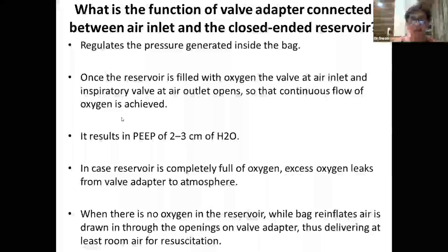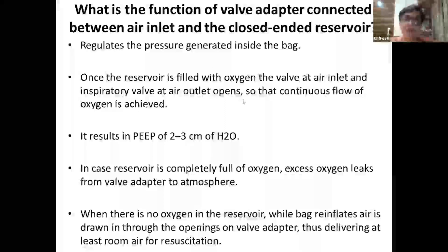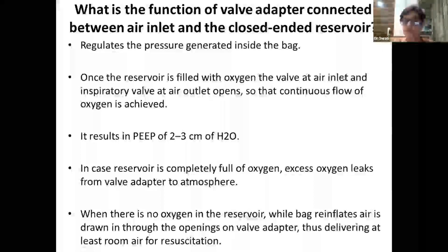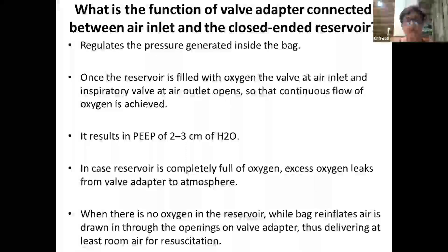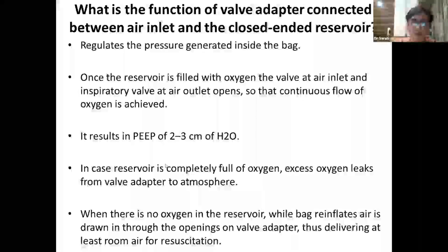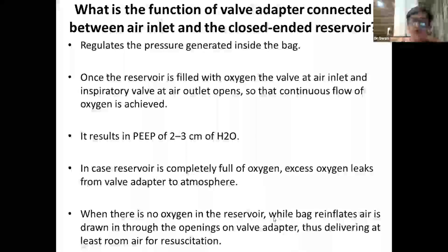The pressure regulatory valve regulates pressure generated inside the bag. Once the reservoir is filled with oxygen, the inlet and inspiratory outlet valves open, achieving continuous oxygen flow and providing a little PEEP. When the reservoir is completely full, excess oxygen leaks out to atmosphere. When there is no oxygen, air is drawn in through the valve adapter openings, delivering at least room air — acting as a safety feature of the closed reservoir bag.